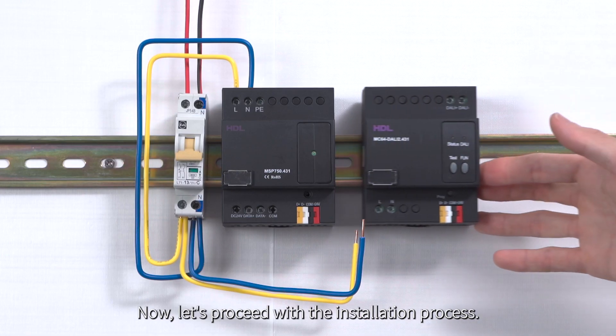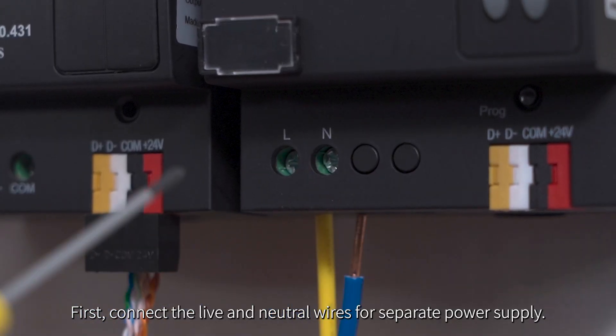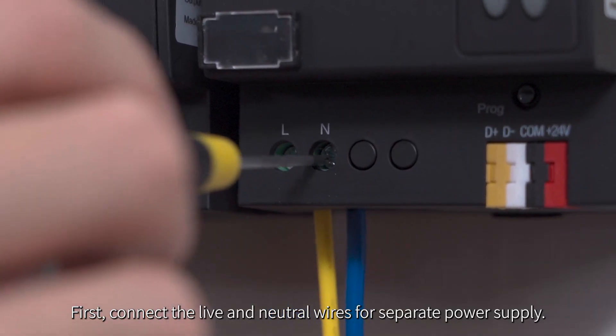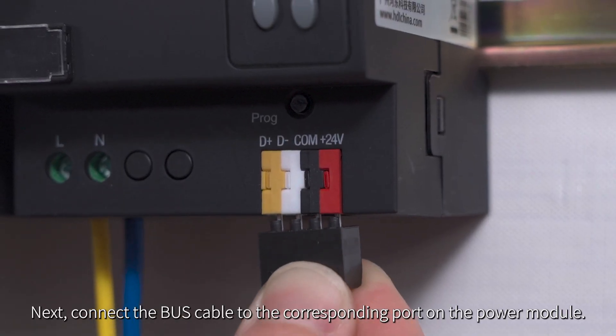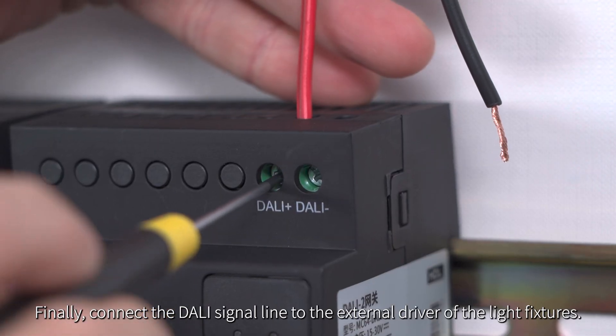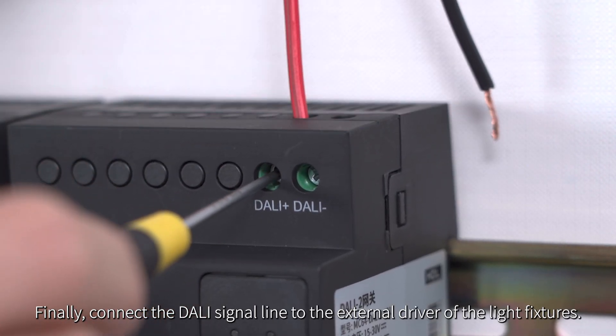Now let's proceed with the installation process. First, connect the live and neutral wires for separate power supply. Next, connect the bus cable to the corresponding port on the power module. Finally, connect the DALI signal line to the external driver for the light fixtures.